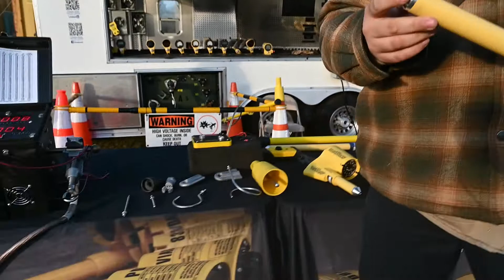Another thing I want to talk about is using accessories on the probe tip itself. So you can make direct contact with the probe tip itself, but what we always recommend is not to take shortcuts. We recommend using the accessories on the end of the probe tip. So maybe you've got a point source, use a straight probe. Maybe you've got an overhead line, use a hook probe. What these accessories do is they just better your depth perception. So say you're working and it's rainy, foggy out, maybe it's nighttime. You want to put one of these accessories on the probe tip. Say you're working overhead and you put this thing on an extendo stick. It just gives you a better chance of not bypassing that line limit mark to start encroaching on those conductive components.